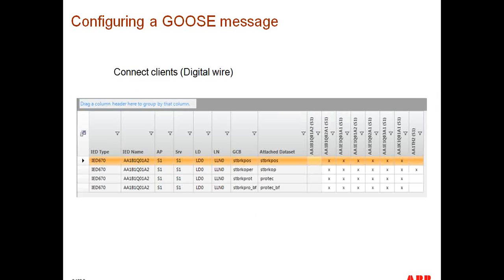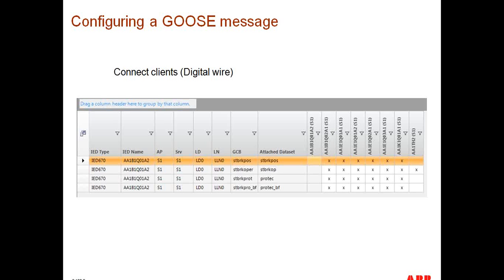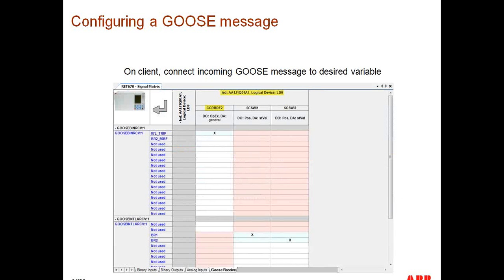Last but not least, I need to connect this GOOSE message or these outputs to other relay inputs. And in this particular case, in this particular piece of software, this is done in a matrix view, where all I have to do is select the relay and then put an X or tie it in a matrix form. Now, this is one part that's very, very, very important to understand.